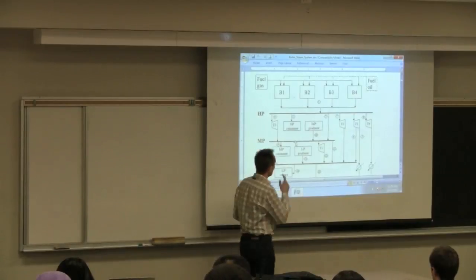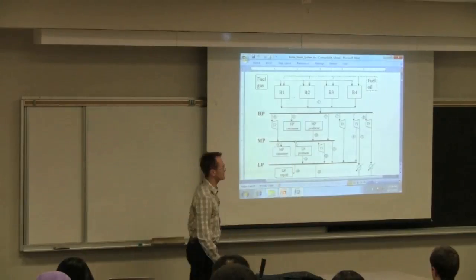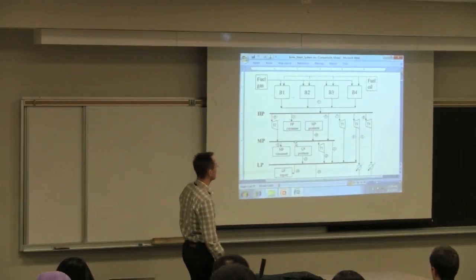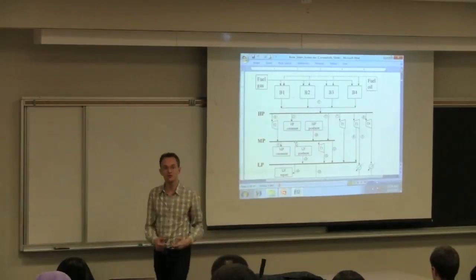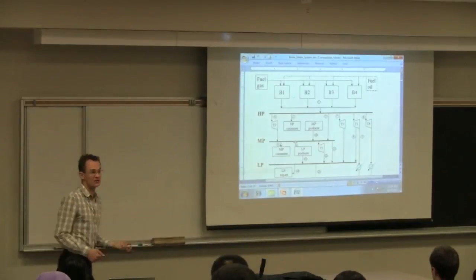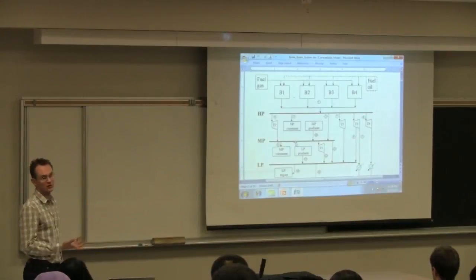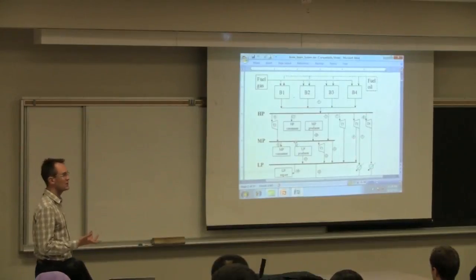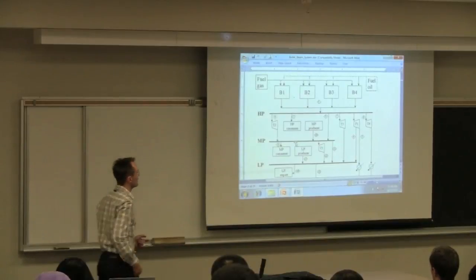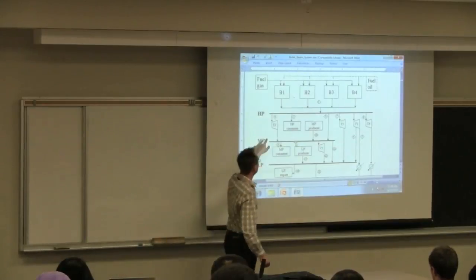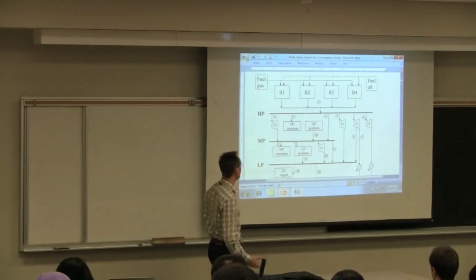To generate medium pressure, we would use turbines to let down that steam from high pressure to medium pressure. And that turbine's work is then recovered. So we can drive pumps with this, we can generate electricity with this potentially. We're getting a credit for our expense here. So we pay money in fuel oil costs, but then we get some of that back by being able to generate useful work over here that can be applied to drive pumps and so forth.